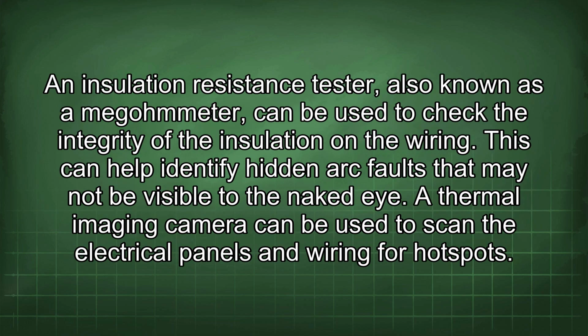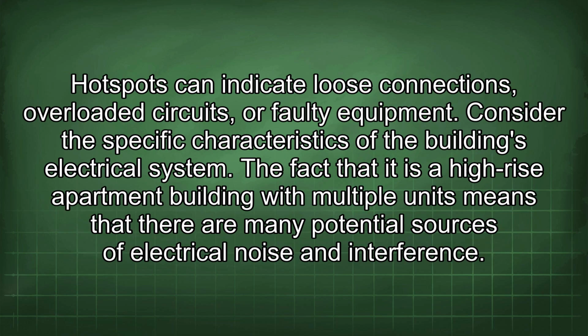An insulation resistance tester, also known as a megohmmeter, can be used to check the integrity of the insulation on the wiring. This can help identify hidden arc faults that may not be visible to the naked eye. A thermal imaging camera can be used to scan the electrical panels and wiring for hotspots. Hotspots can indicate loose connections, overloaded circuits, or faulty equipment.